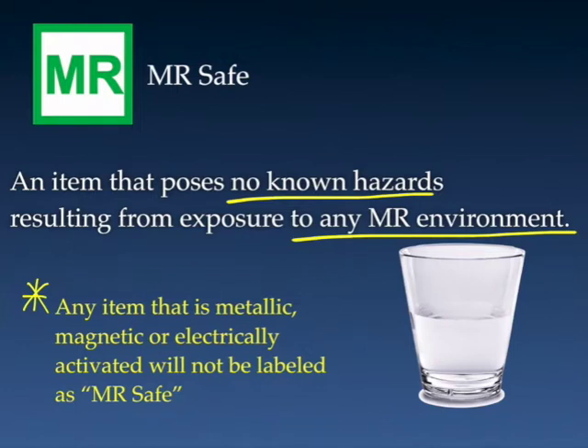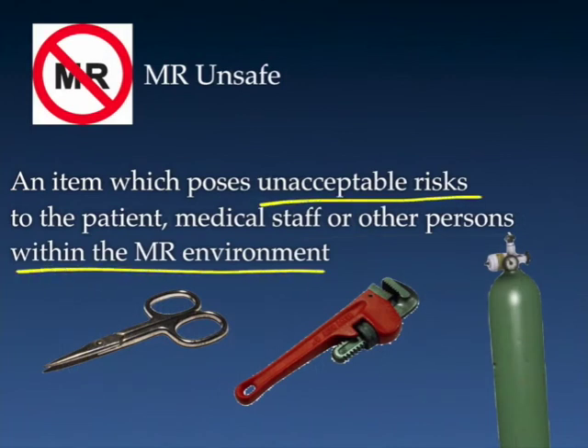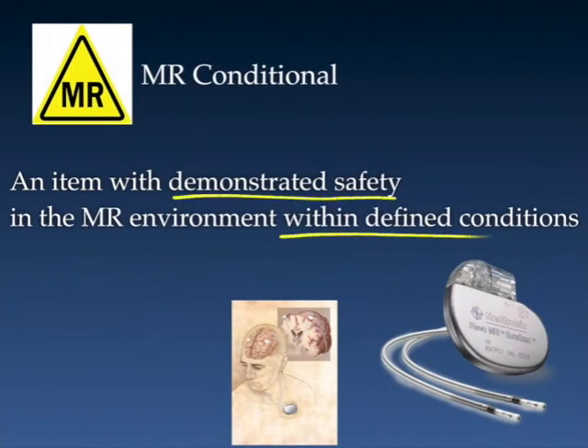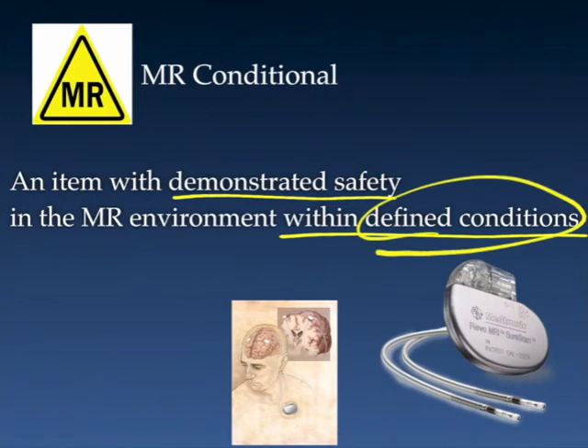We need to stop referring to devices such as pacemakers and ICDs which have MR labeling as safe. MR unsafe is pretty straightforward — it's an item that poses unacceptable risk to the patient, medical staff, or other persons within the MRI environment. MR conditional is the labeling applied to an item that has been tested and demonstrated to be safe in the MRI environment within defined conditions. That's a very important component of this labeling: safe within defined conditions.